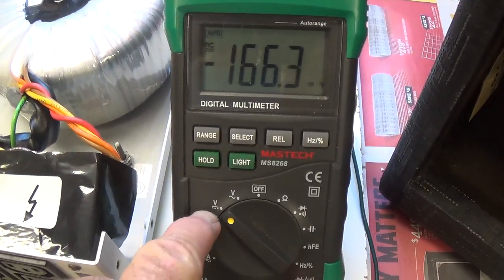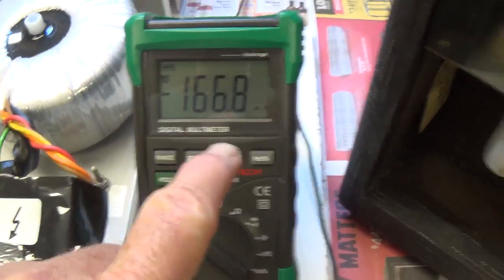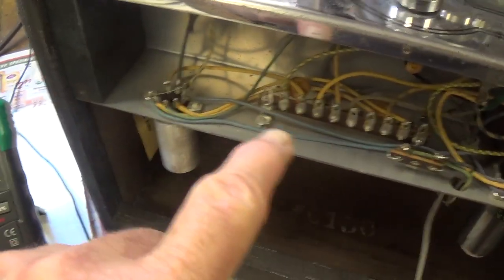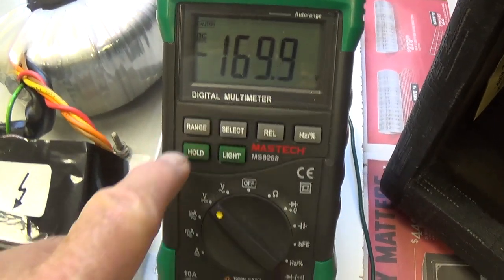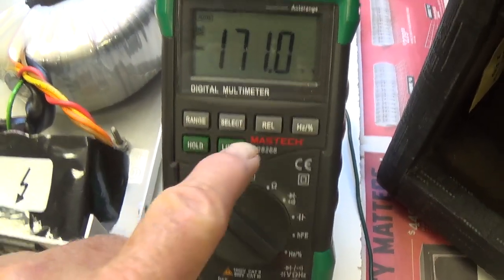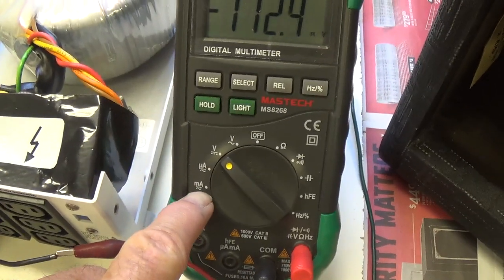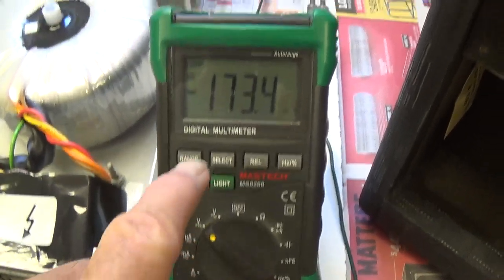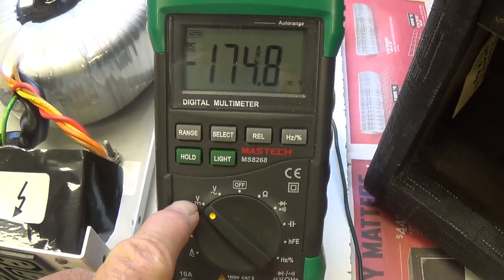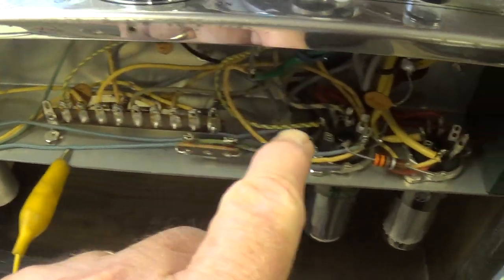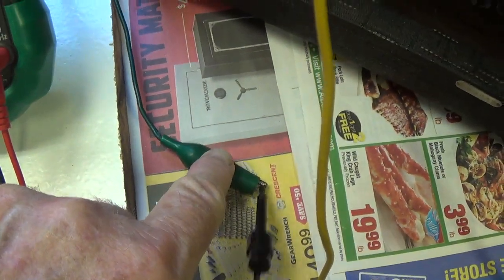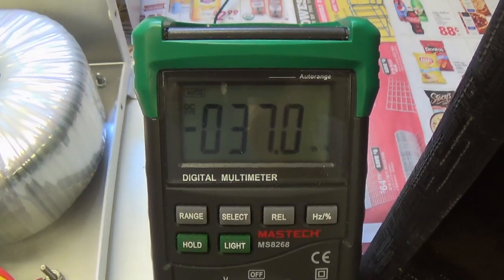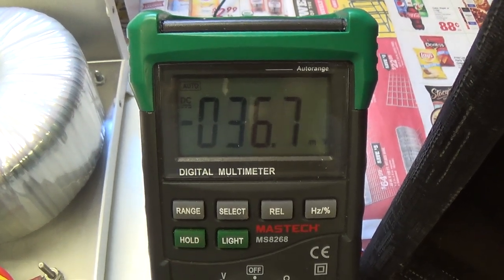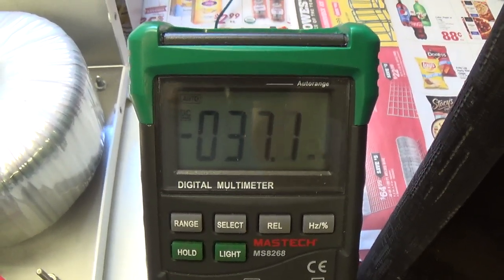Now I'm going to be using DC volts as my criteria of judgment if a potential exists, simply because I don't want to take a risk of damaging my meter by exposing it to a high flow of current. So we'll be measuring volts of potential between different locations in the circuit and the grounding clip of our oscilloscope. And I can assure you that any potentials we encounter will not be ghost voltages, but will be the real thing.